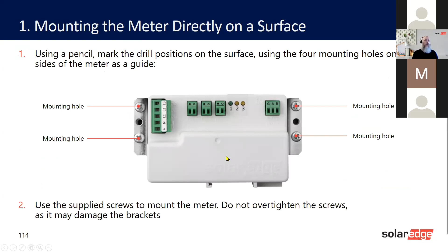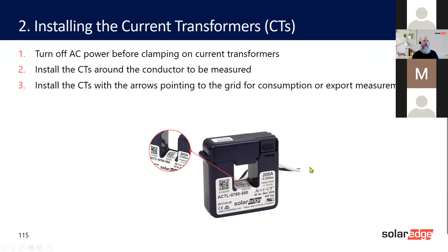There's your CT, and if you look in here, you can see that the CT has an arrow pointing. This is what you need to make sure points to the grid. Again, these are different amps. This is 200 amps. Most importantly, you must use the SolarEdge CTs because we run on 0.333 volts as opposed to a ratio. So you must use these ones. If you don't, it won't work basically.